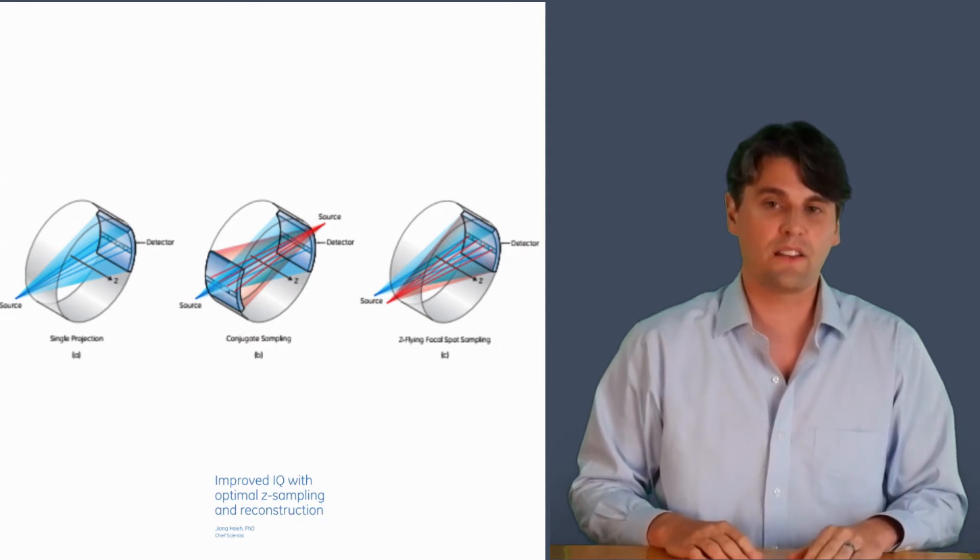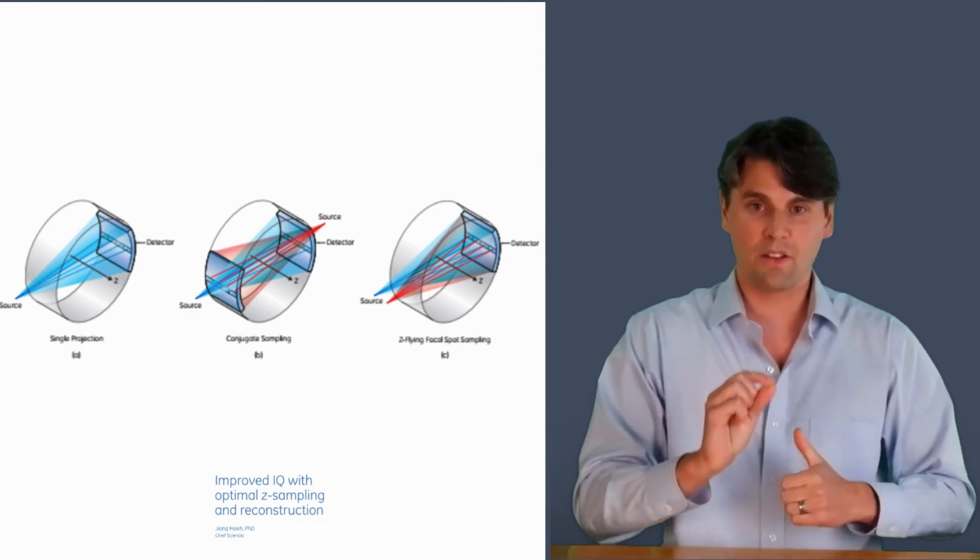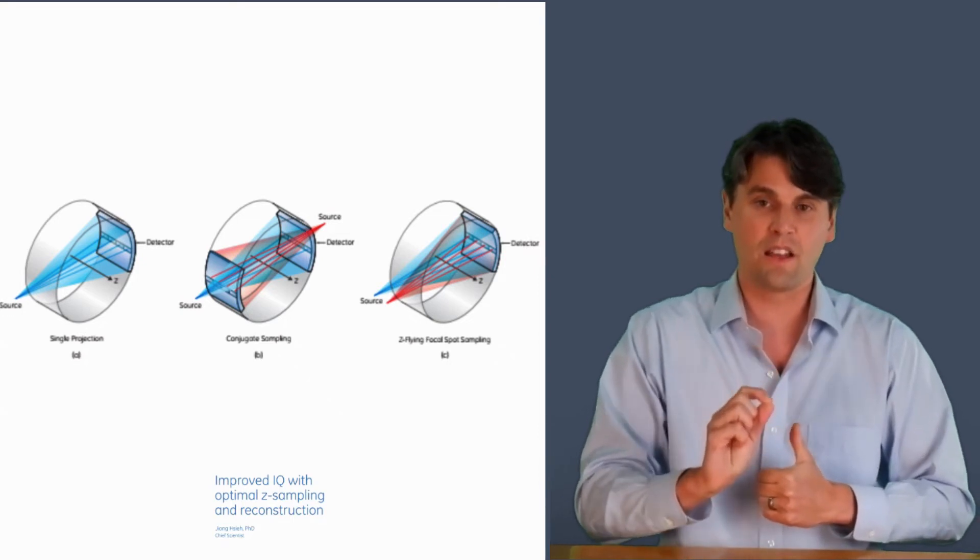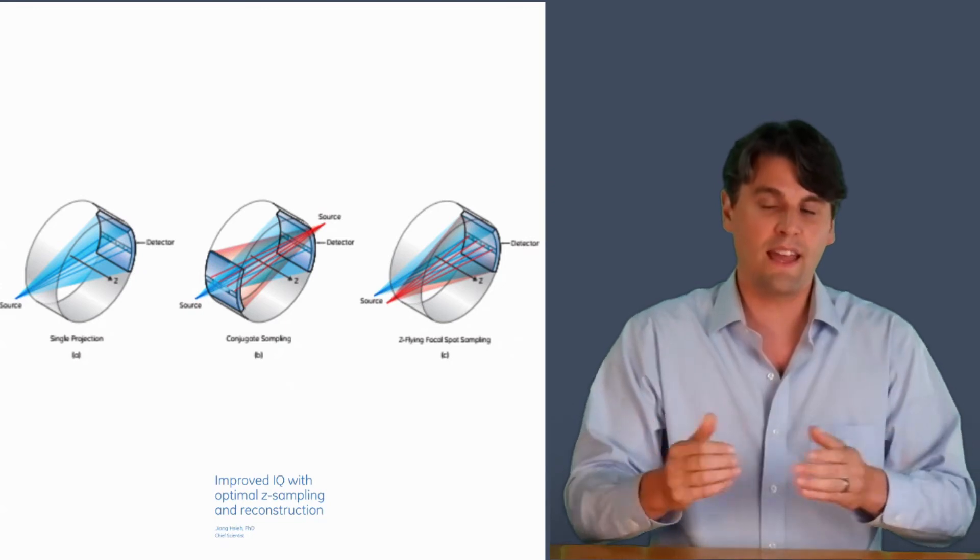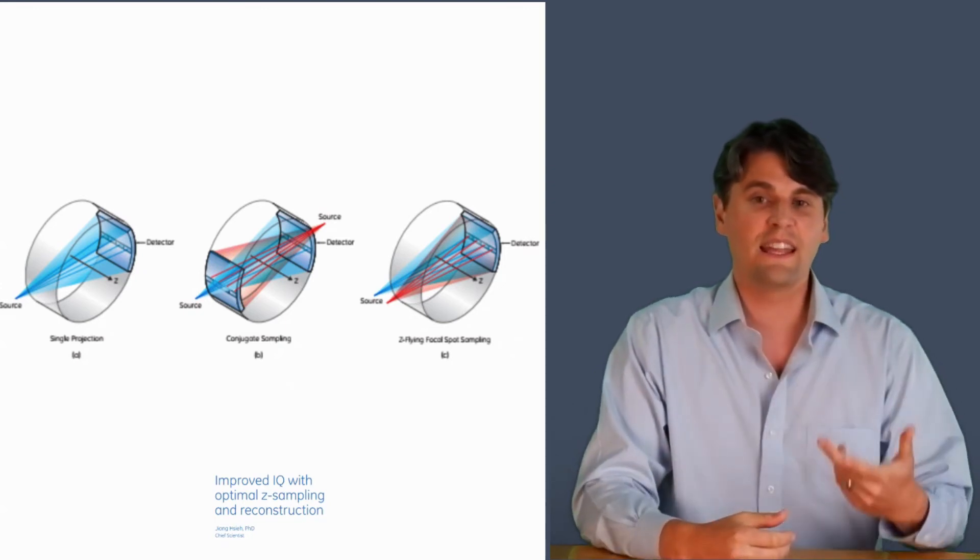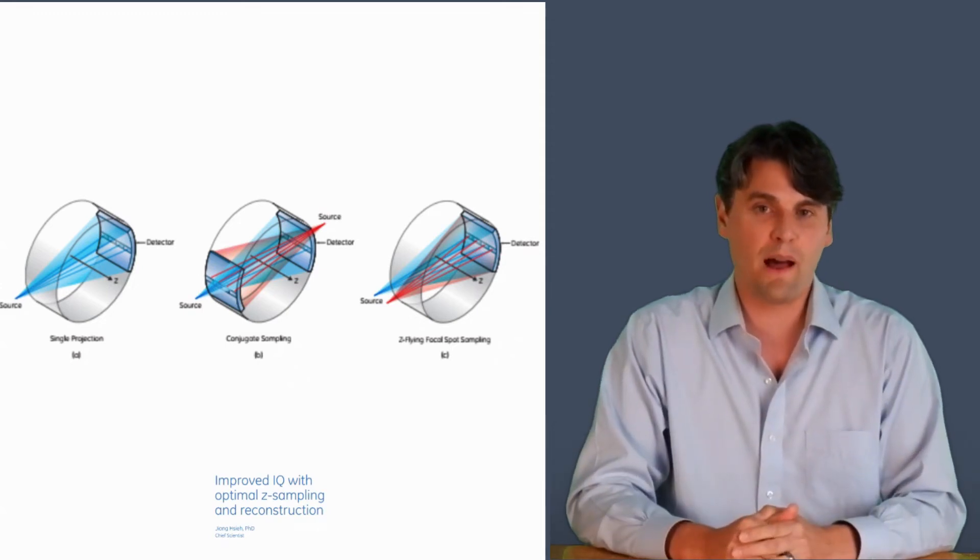One way is to use what is called focal spot deflection in the z-direction. And if you do focal spot deflection in the z-direction, then your focal spot is moving essentially up and down in this direction as the tube is rotating around. And you can take those acquisitions and increase your sampling by having that focal spot deflection.